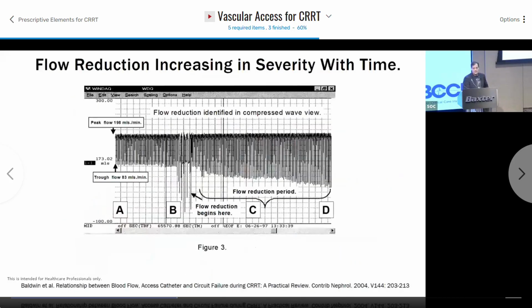Now, this was measured by Ian Baldwin. I mentioned that he has a flow probe for this, and you can see at the beginning of therapy, he was doing just fine. Then they rotated the patient. They had some problems, and we don't know what happened to the catheter tip or anything, but he started to have bigger periods of flow reduction. And remember, these are pulsatile flows because it's a peristaltic pump. That's why you get pulsatile flows. And he had all these periods of flow reduction, and this led to catheter failure. And he's actually published a series on this, which is very provocative.